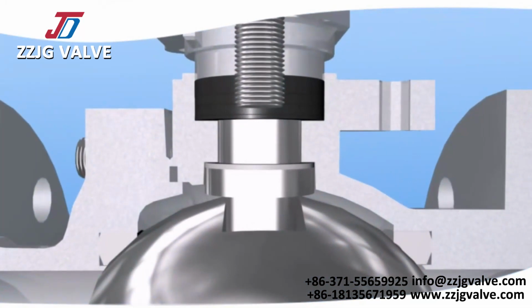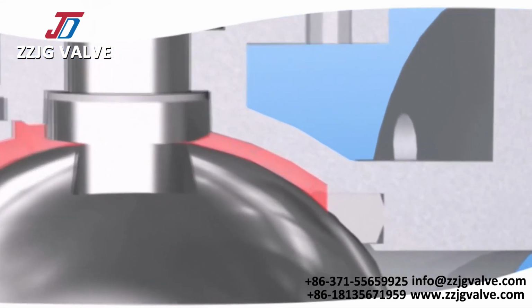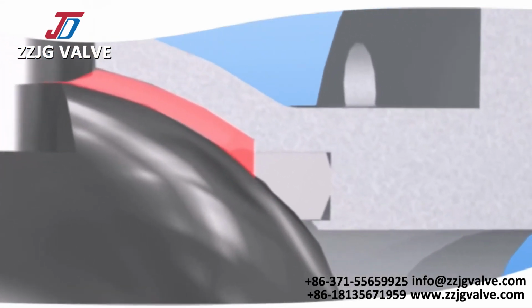6. Middle cavity self-relieving structure. The medium in the middle cavity may have abnormal pressure rise caused by medium temperature changes in the piping system. In this case, the medium in the cavity will be relieved automatically, thus realizing the self-relieving function.